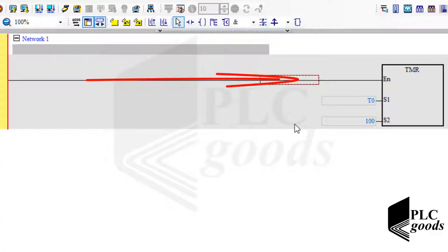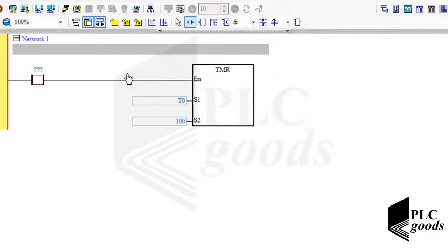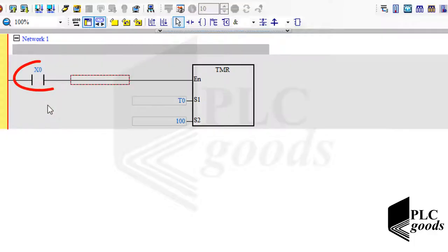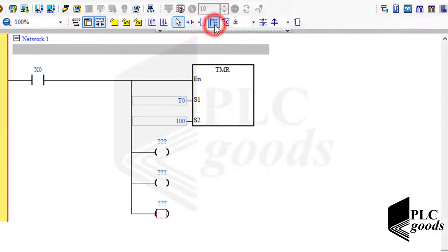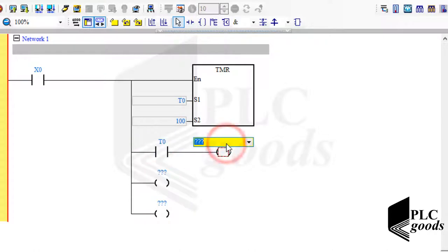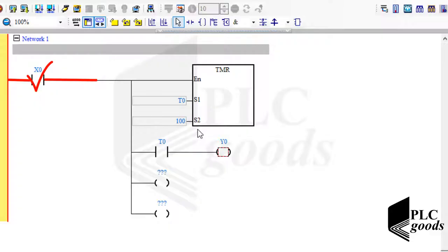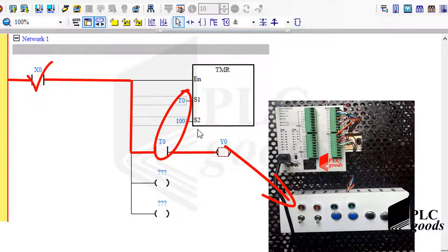The timer will start its work immediately after the PLC goes to run mode. Let's use a contact before it so I can enable or disable the timer with the first digital input. Now let's see some examples of using the T0 timer. I can use a normally open contact to turn on an output. Based on the program, if the first digital input is activated and the timer reaches 10 seconds to activate its coil, the virtual power will reach the output, so the PLC will turn on the first LED after 10 seconds.